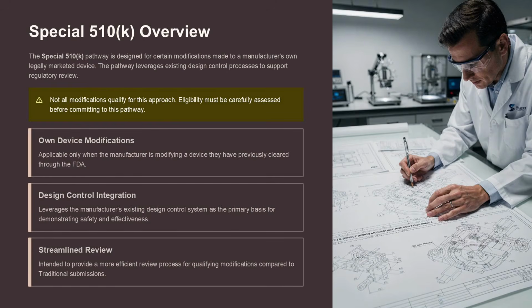The special 510(k) pathway is designed for certain modifications made to a manufacturer's own legally marketed device. The pathway leverages existing design control processes to support regulatory review. Not all modifications qualify for this approach, so eligibility must be carefully assessed before committing to this pathway.